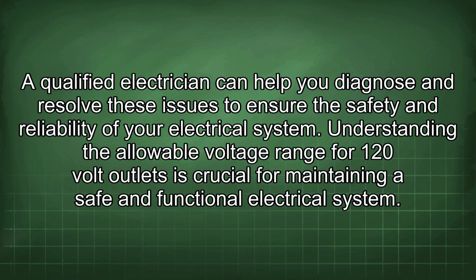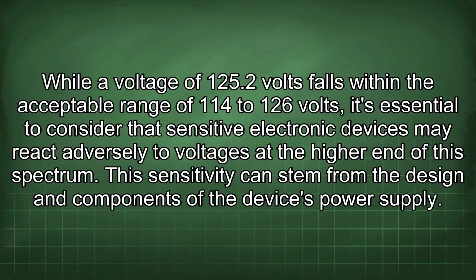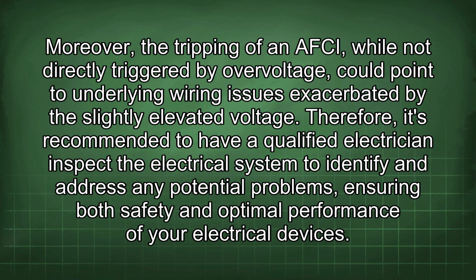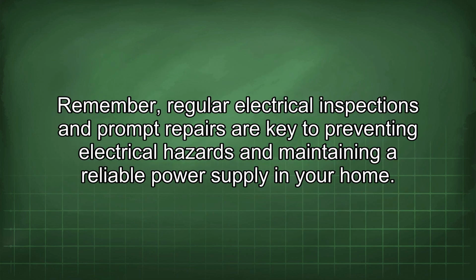Understanding the allowable voltage range for 120-volt outlets is crucial for maintaining a safe and functional electrical system. While a voltage of 125.2 volts falls within the acceptable range of 114 to 126 volts, it's essential to consider that sensitive electronic devices may react adversely to voltages at the higher end of this spectrum. This sensitivity can stem from the design and components of the device's power supply. Moreover, the tripping of an AFCI, while not directly triggered by overvoltage, could point to underlying wiring issues exacerbated by the slightly elevated voltage. Therefore, it's recommended to have a qualified electrician inspect the electrical system to identify and address any potential problems, ensuring both safety and optimal performance of your electrical devices. Remember, regular electrical inspections and prompt repairs are key to preventing electrical hazards and maintaining a reliable power supply in your home.